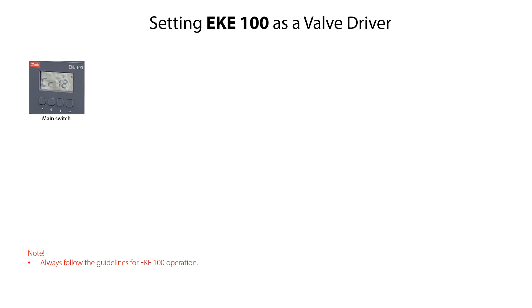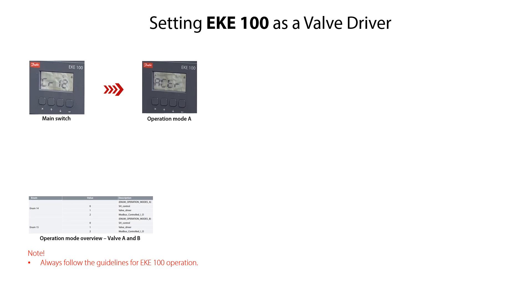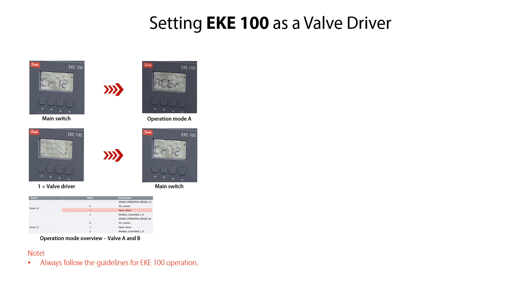To configure the EKE100 as a valve driver for valve A, from the main switch CR12 mode, press the arrow down key to access the operation mode A, specified as ACTR. Press the enter key to access the available operating modes. The value should be set as 1 for valve driver. Press the arrow up or arrow down keys to get the needed value, then press the enter key to confirm value 1 and return to the ACTR mode. Press the arrow up key to return to the CR12 mode, from where you can access and set relevant valve driver parameters by pressing the arrow down key.